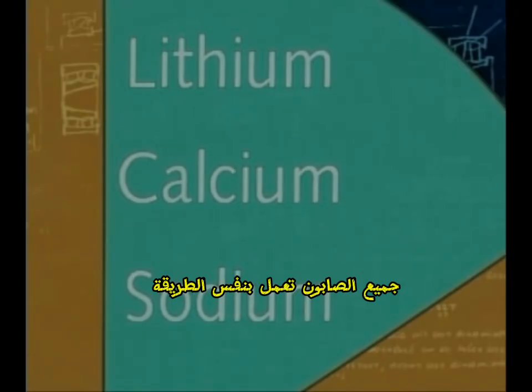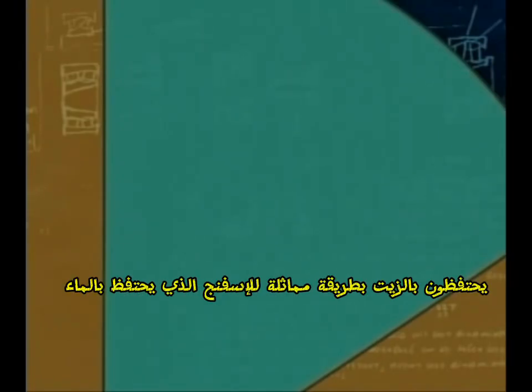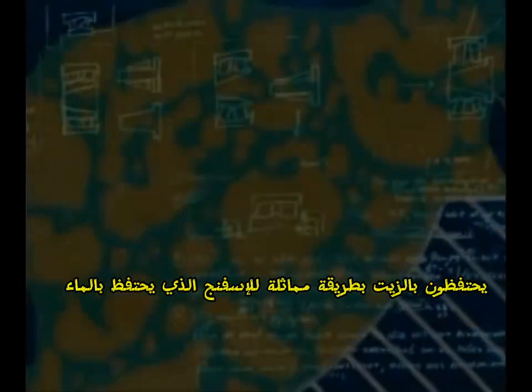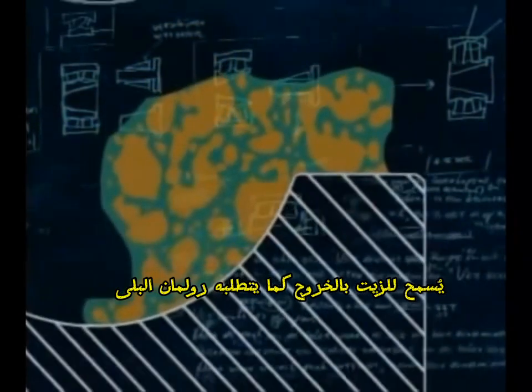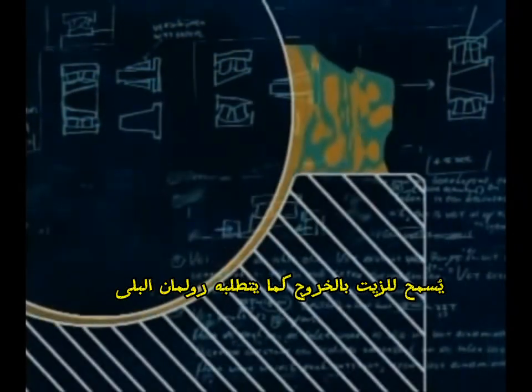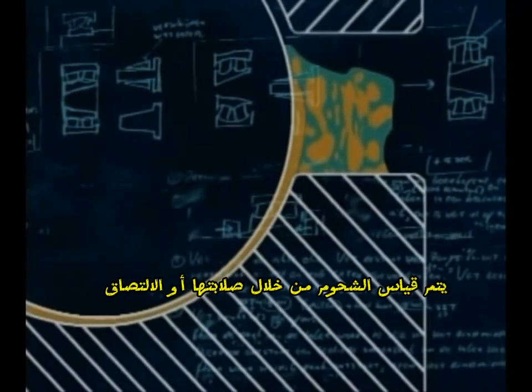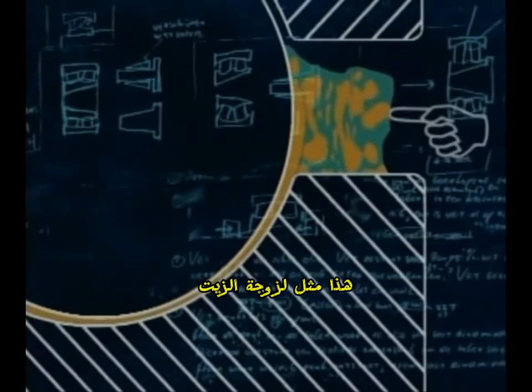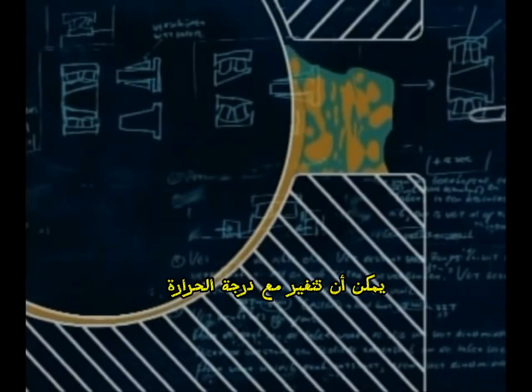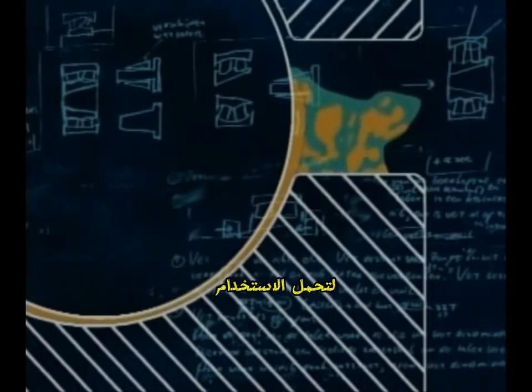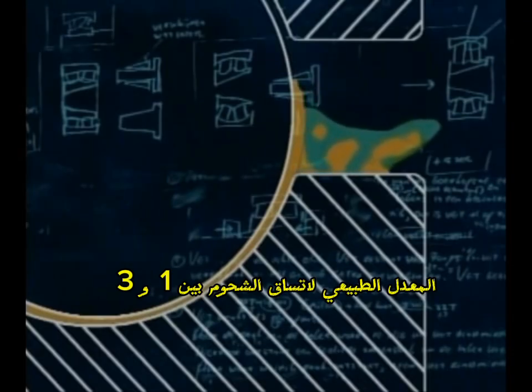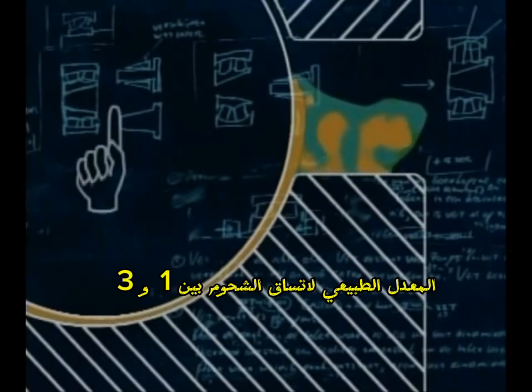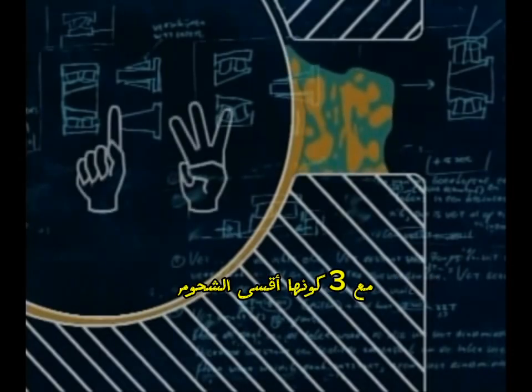All the soaps function in the same way. They retain the oil in a similar manner to a sponge retaining water. The oil is allowed to bleed out as the bearing requires it. Greases are measured by their stiffness or consistency. This, like the oil viscosity, can change with temperature. For bearings, use the normal range of grease consistency, between 1 and 3, with 3 being the stiffest.